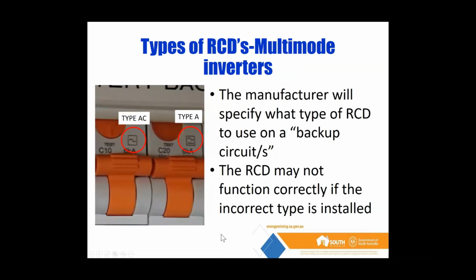When you are installing a multimode inverter and you have to put RCDs on the standalone circuits, a big issue that guys tend to trip up on is what type of RCD is required. Now, I haven't written it in here, but AS 4777 Part 2 actually mandates the manufacturer of the inverter to tell the installer what type of RCBO or RCD to install. They'll mandate it has to be a type A or a type AC. Once you have that, because you've read the instructions, you can then install the correct type of RCBO.